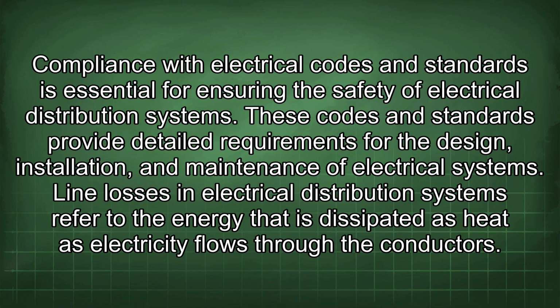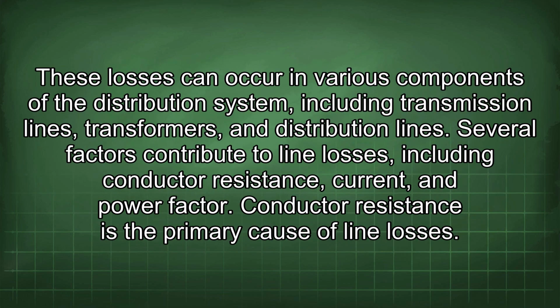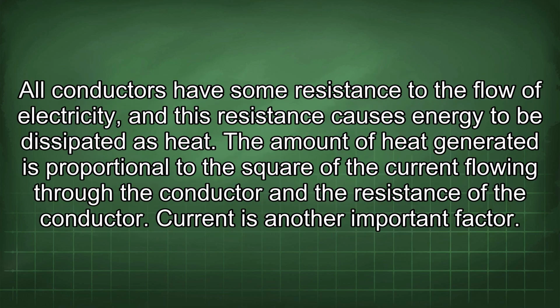Line losses in electrical distribution systems refer to the energy that is dissipated as heat as electricity flows through the conductors. These losses can occur in various components of the distribution system, including transmission lines, transformers, and distribution lines. Several factors contribute to line losses, including conductor resistance, current, and power factor. Conductor resistance is the primary cause of line losses. All conductors have some resistance to the flow of electricity, and this resistance causes energy to be dissipated as heat.